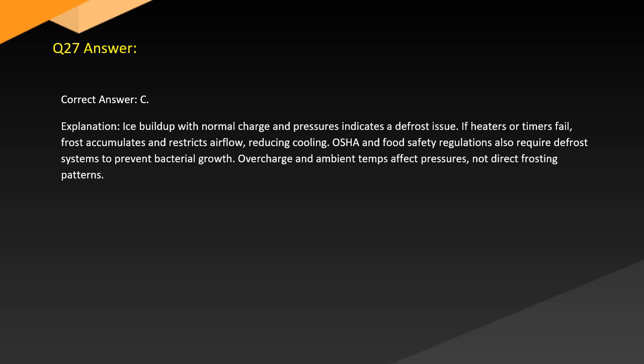Answer. Correct answer C. Explanation. Ice buildup with normal charge and pressures indicates a defrost issue. If heaters or timers fail, frost accumulates and restricts airflow, reducing cooling. OSHA and food safety regulations also require defrost systems to prevent bacterial growth. Overcharge and ambient temps affect pressures, not direct frosting patterns.